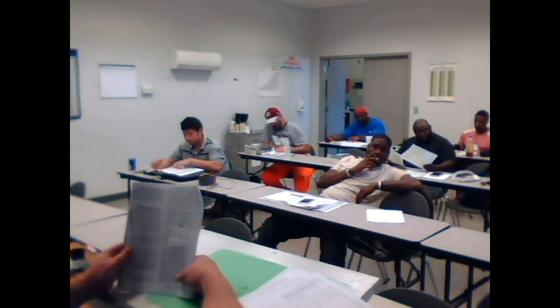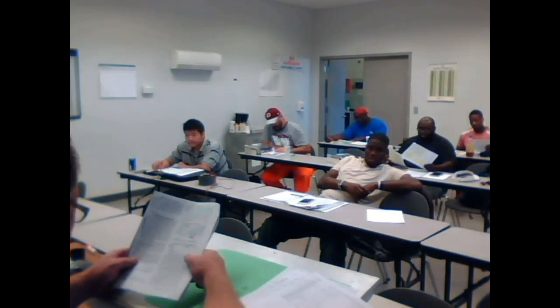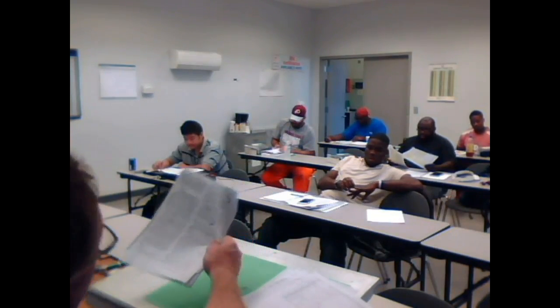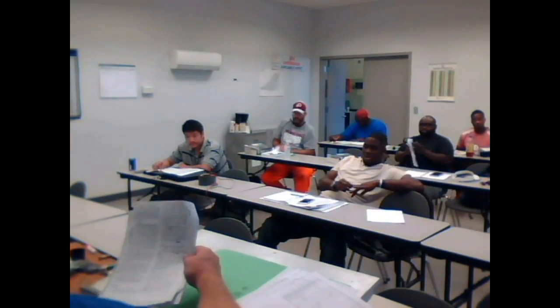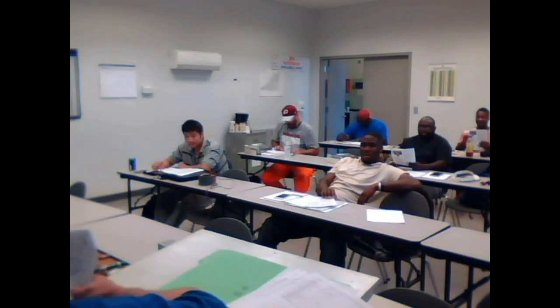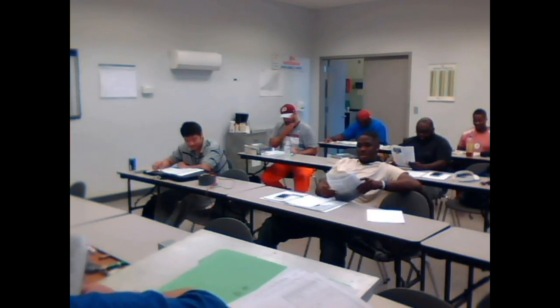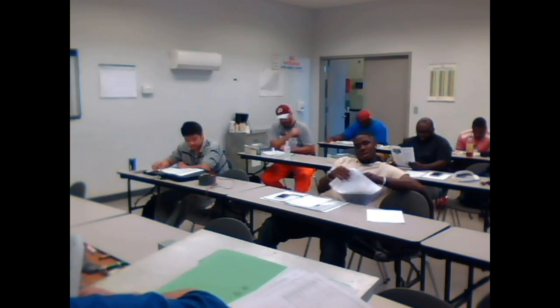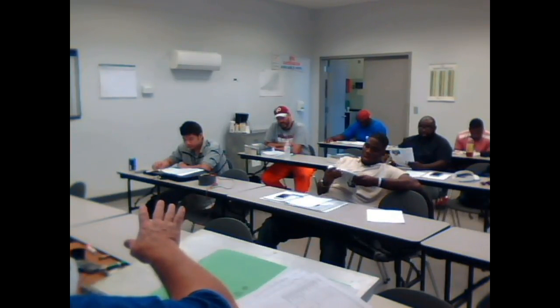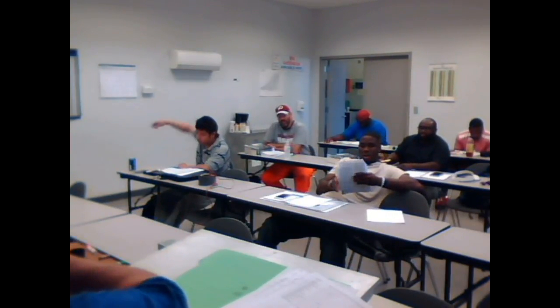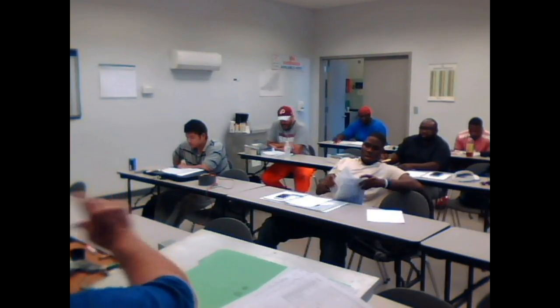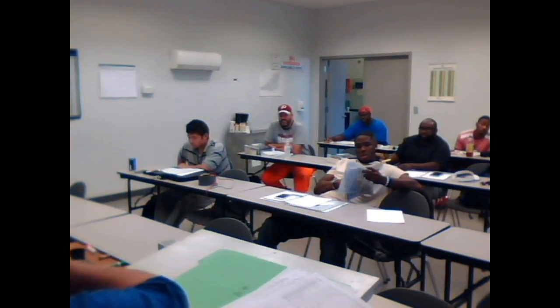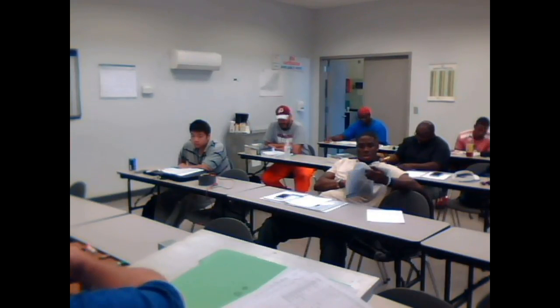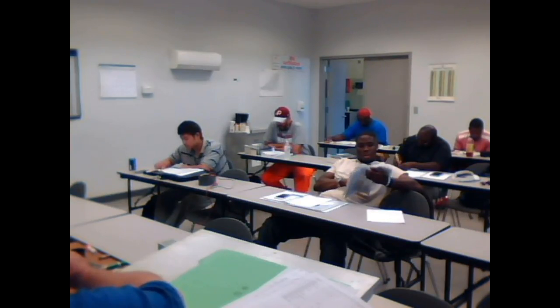Lubrication. We got some information here you're not going to find anywhere else. Okay, that's a reason never to lose this. If you're looking, you call me up in 10 years and you go, Clay, I'm looking for some information on lubrication. Electric motors that require periodic lubrication. This is not to be confused when you pick one up and it says permanently lubricated. That means whatever you do, do not lubricate. Should be checked and oiled with care and common sense.